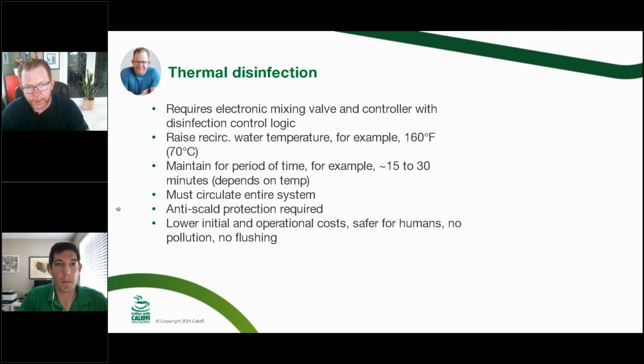Yeah, so thermal disinfection obviously is very important. Max and I have already touched on there's just certain applications where you don't want to be taking any chances. Schools and hospitals and things of that nature. We need to make sure that we do have a disinfection cycle. This again comes back to what Max said, is understand it's not going to be an anti-scald device. If we've got a disinfection cycle on this, and if it's in the process of running that cycle, we don't want somebody turning a tap on because they will end up with considerably hotter water, like 160 degrees coming out, and that's a bad news situation.